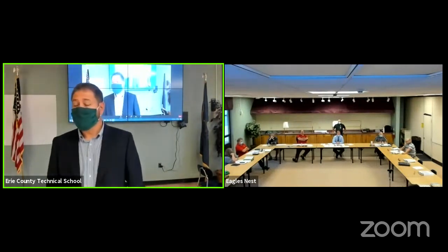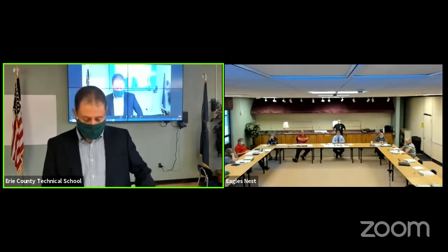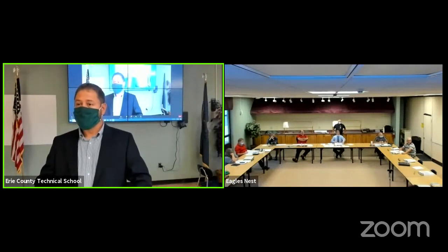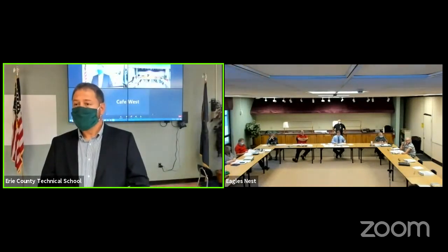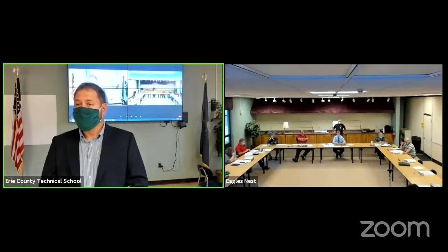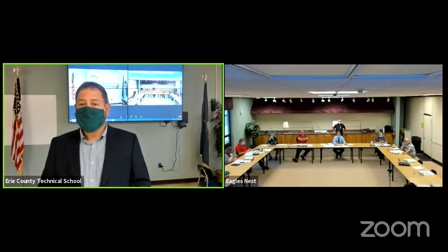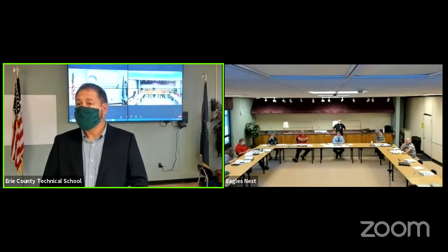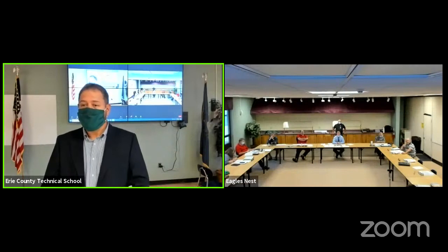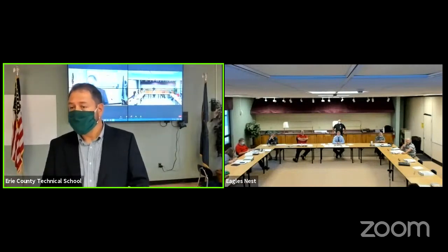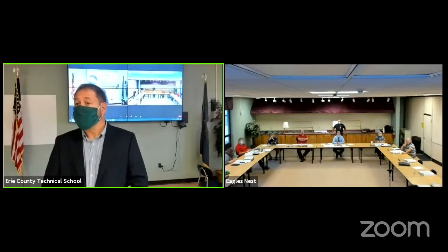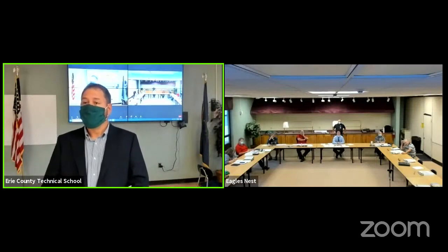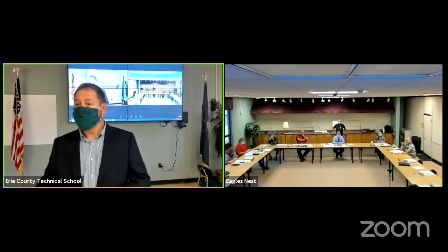I see at your maintenance cost per year that the chilled system is roughly $8,000 more a year you're predicting to maintain. What is the biggest reason for that extra $8,000? The biggest reason is probably the chillers themselves. Is that physical parts or man hours? More on man hours. I don't anticipate, unless you have a compressor or something go bad on a chiller, there's not a lot of parts and pieces you're going to replace. So it's more just general maintenance - cleaning, flushing the system, maintaining the glycol, making sure the percentages are correct in the solution and whatnot.